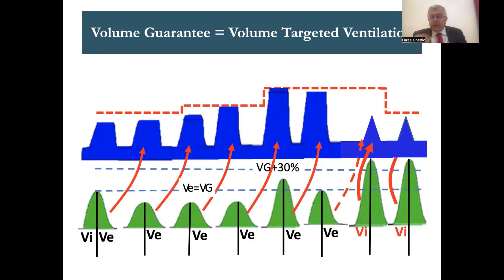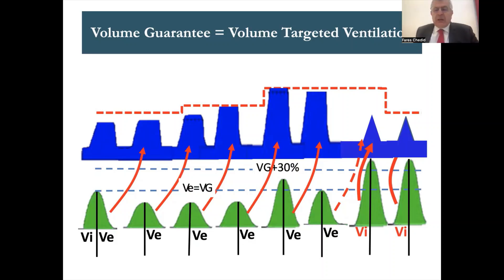This is the principle of volume guarantee — the pressure produces volume and the volume orders the pressure of the next breath. We use the expired volume because we know it came from the lung. If there is leak, the machine compares inspiratory and expiratory flow, measures the leak, and performs leak compensation so that the machine does not give more PIP simply because the expired volume appears low due to leakage around the tube.